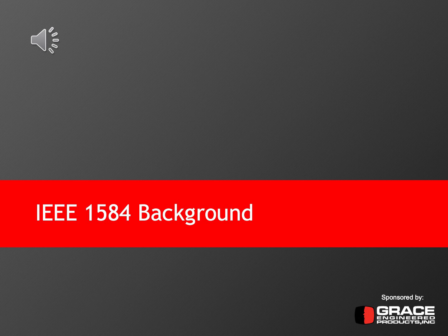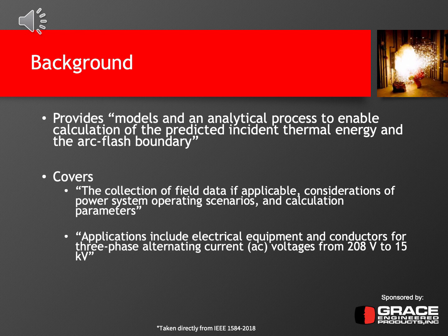So now that we know the purpose, the next step is to get a little bit of background, a history lesson on IEEE 1584, and see where the standard has developed over time, what changes have occurred, why things were done the way they were done, and why the new equations have been adopted and why they're a lot more complicated than the original 2002 edition. IEEE 1584 provides a model and an analytical process that enables the calculation of a predicted incident thermal energy and the arc flash boundary. What this means is it allows you to calculate the amount of energy at a specific distance away from the energized equipment should an electrical arc occur.